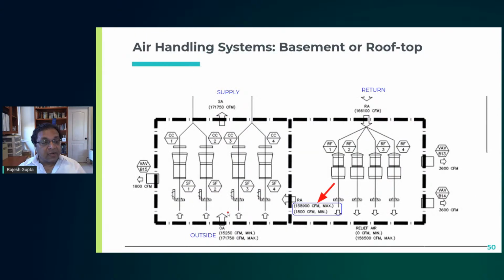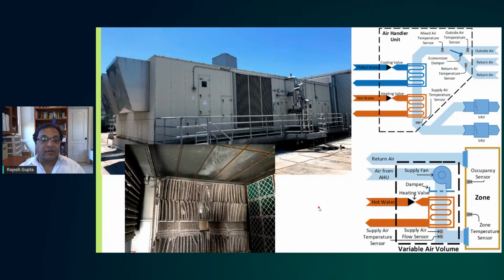If you look at the entire air handling system for the entire building, you have big fans supplying air to the building, taking the return air and relieving that air to the outside, taking the outside air, and then there is some recirculation that happens here. Okay, so this is for the entire building. This is the schematic diagram, and this is how it looks in reality, on the roof, for example. This is a typical air handler where you have air entering either from outside or from the recirculation, and these are the filters, supplying the various air handling units and the various zones.